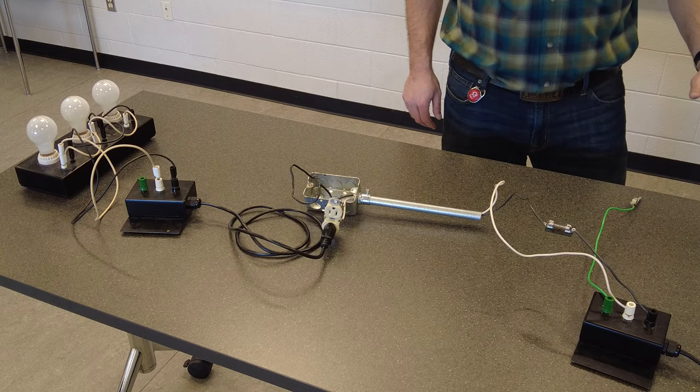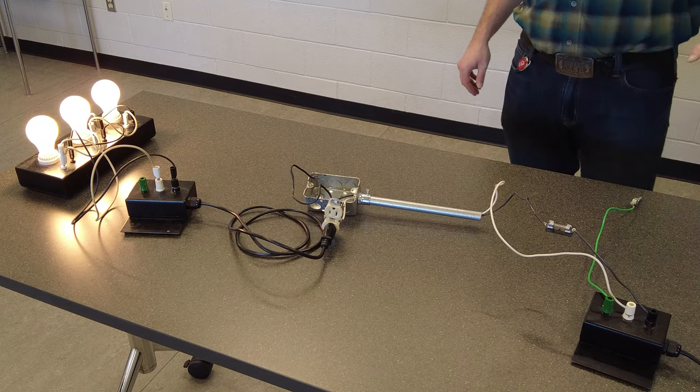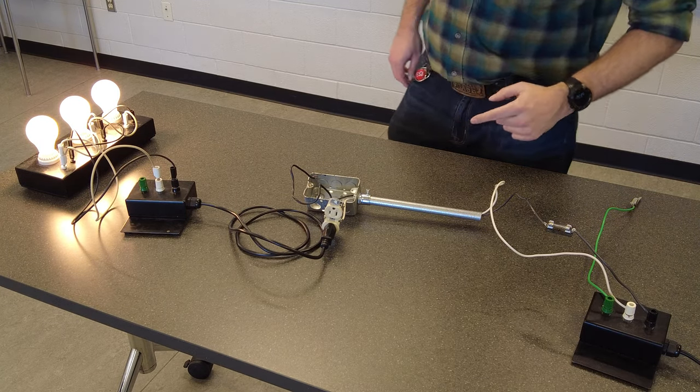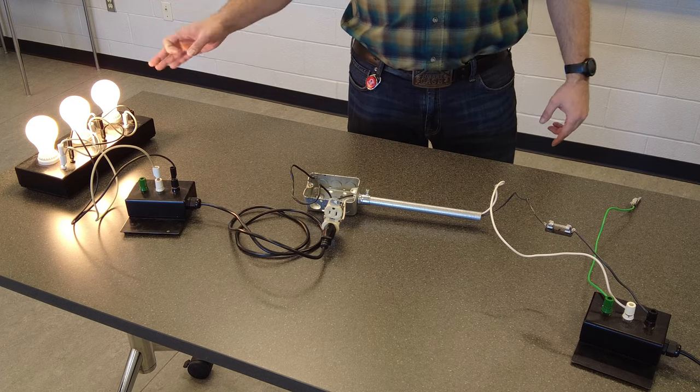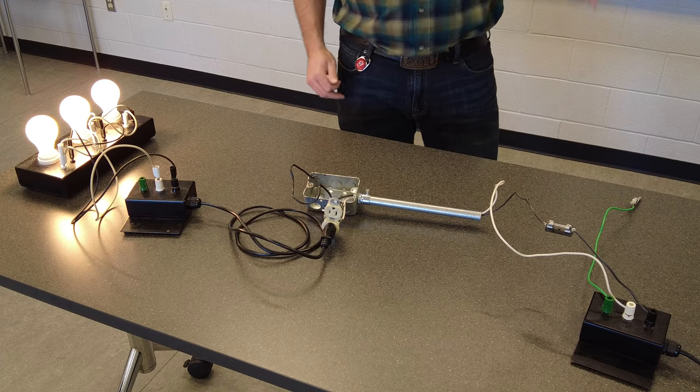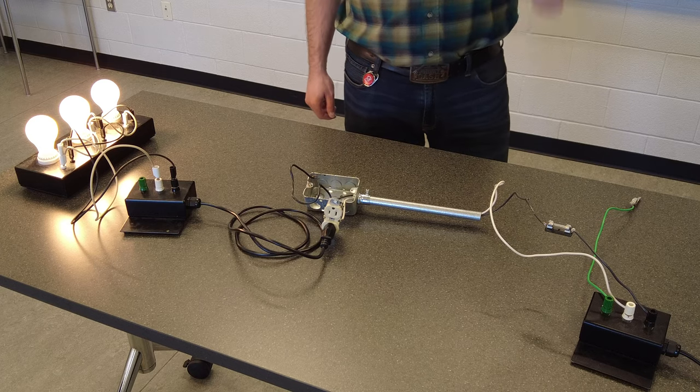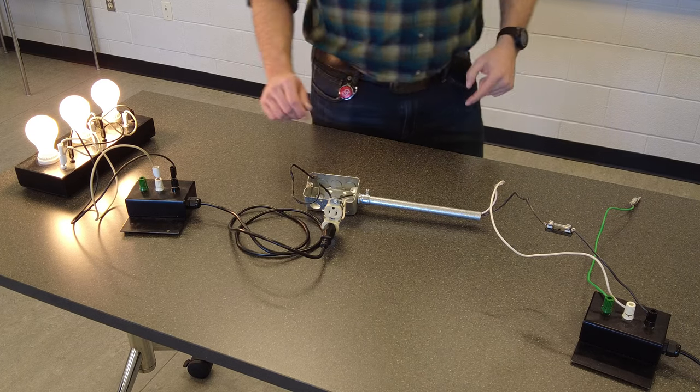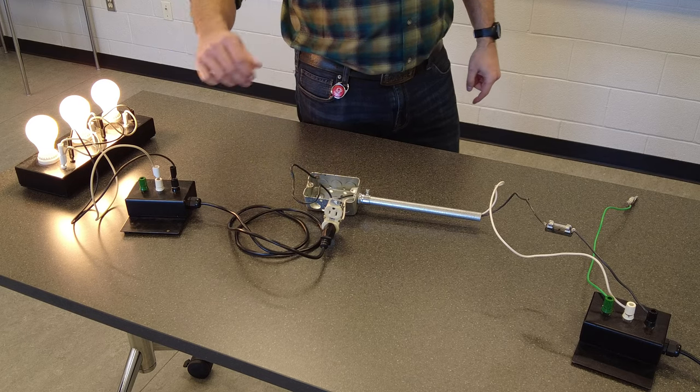We're going to disconnect it and see what happens in this system again. So I'll re-energize - notice first off, with the bonding sacrificed, the loads still energize. The loads are still on. This will not indicate to you that there's a problem with your bonding connection. The next thing I'm going to do is repeat exactly what I did in the previous demo. I'm going to touch this little dangerous hook here to the side of my box, and we're going to see what happens.